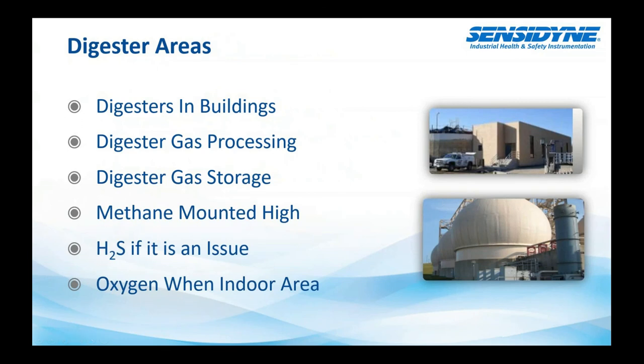Digester areas, digester buildings, gas processing, gas storage, anything that's enclosed and around these sort of environments, you're going to want to monitor for, again, O2, H2S, and LEL. See a common theme here. These are the basic three that we're monitoring for in these areas where the sludge is producing this biohazard gas.